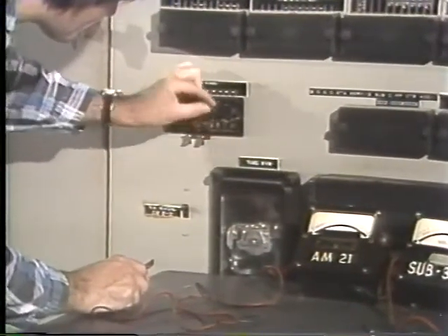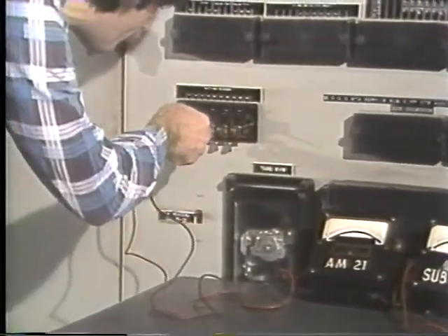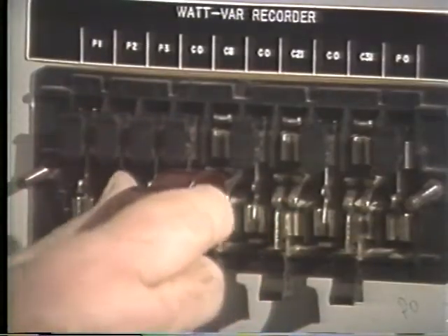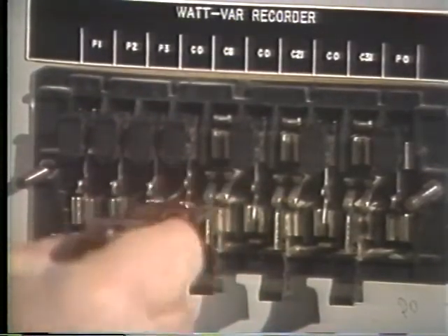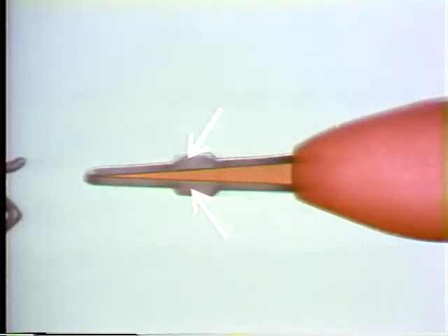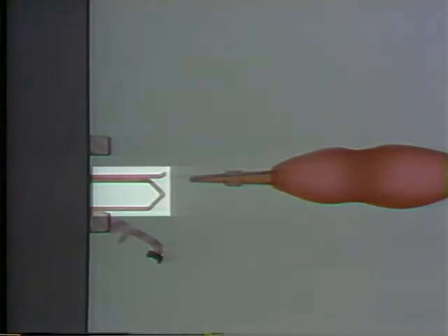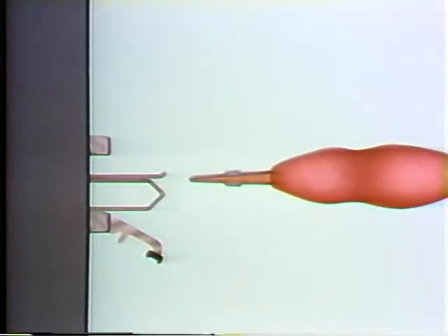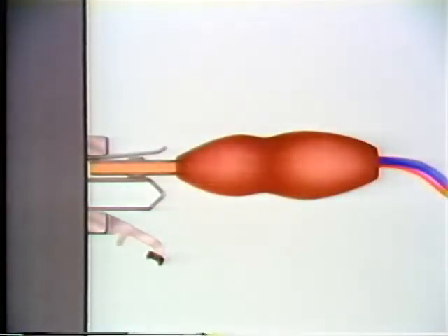A lot of meter panels have special test terminals that make this whole process unnecessary. With the right kind of probe, you don't have to open the circuit at all. This probe has two conductors that are separated by an insulator over their entire length. These test terminals are made of springy metal. Normally, their spring tension holds them tightly together and keeps the circuit closed. But when you insert the probe, the terminals spread apart. The circuit is never open, and the portable meter is safely connected in line.